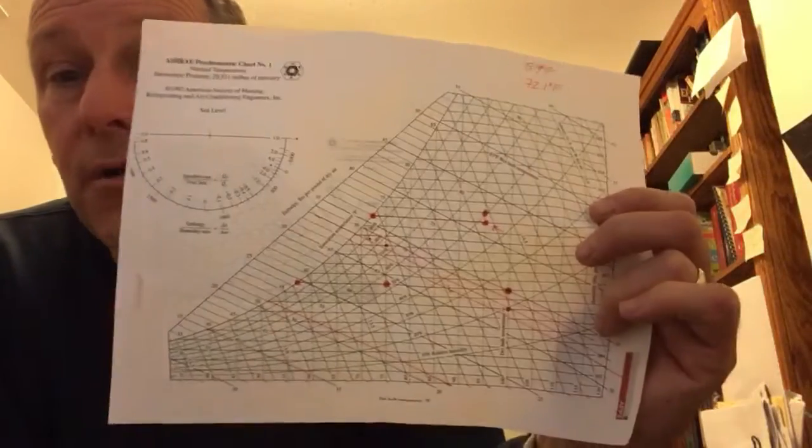The second thing to observe is the dew point was the same for both the first example and the last example. And what was the same about the first example and the last example? Well, in both cases, they had the same moisture level, 0.010. It turns out that moisture level, or our specific humidity, entirely determines what the dew point is. Okay, good enough. That is it.